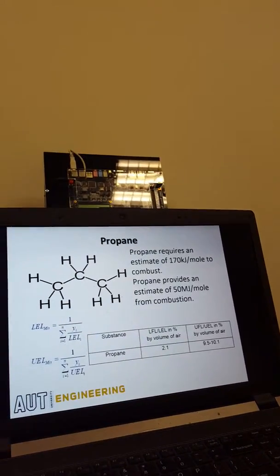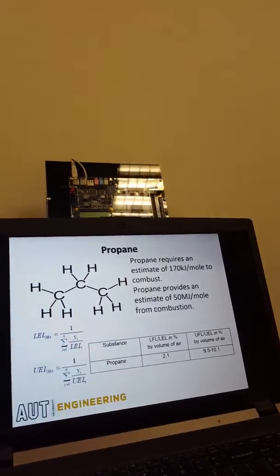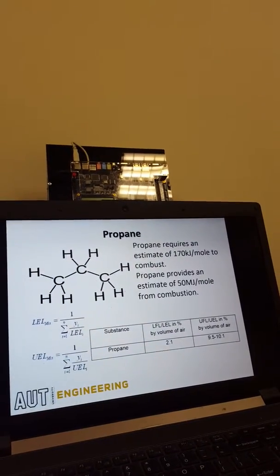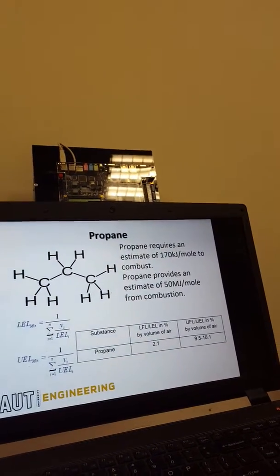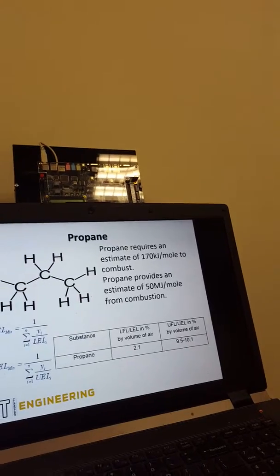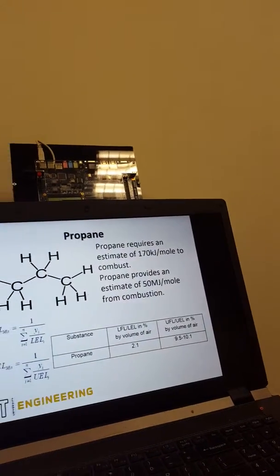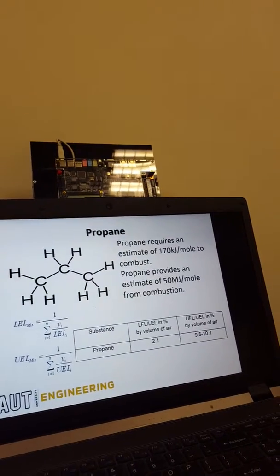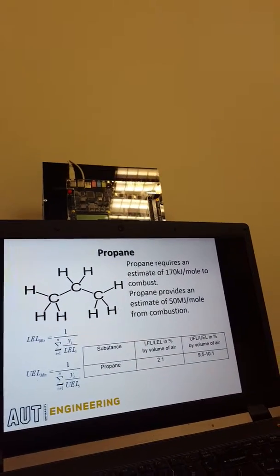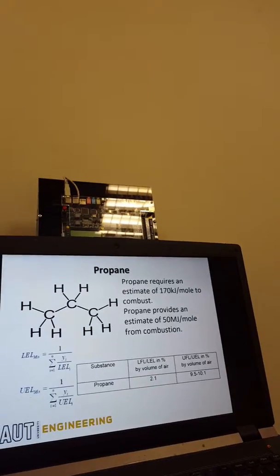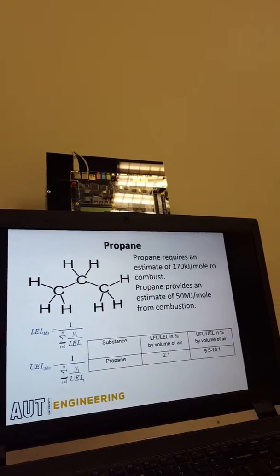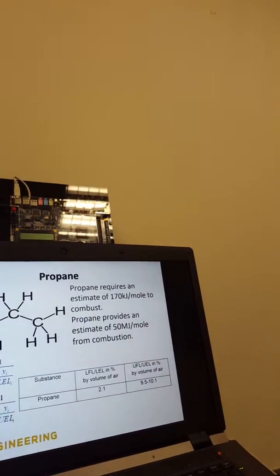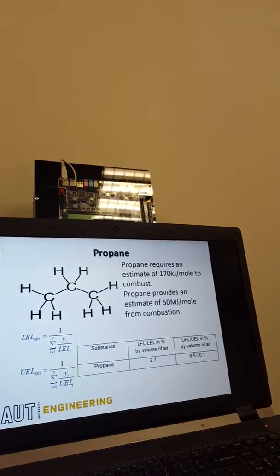But the behavior of the propane is that the percentage of it to air where it does combust is from 2.1% to somewhere around 9.5 to 10.1%. These are called the lower explosive limit and the upper explosive limit. If the percentage in air is below 2.1%, there's not enough propane to be ignited, and if it's above 9.5 to 10.1%, there's not enough oxygen and the system chokes.